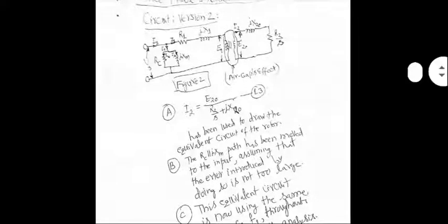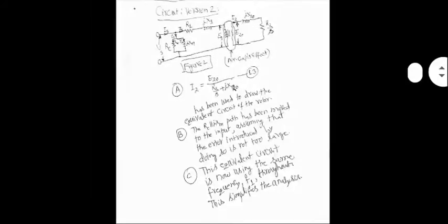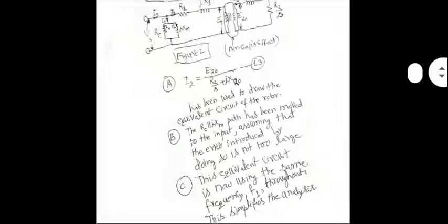Okay, so in this equivalent circuit, there are two important differences. One is that on the rotor side, I've got only standstill values, and on the stator side, I have moved the core effect to the position right at the input supply. That's an assumption I'm making, that it will not change things too much. Now this equivalent circuit works at the same frequency F1 throughout.